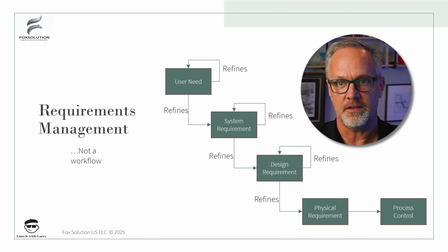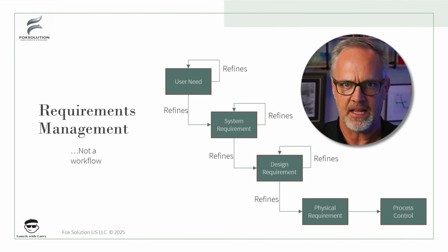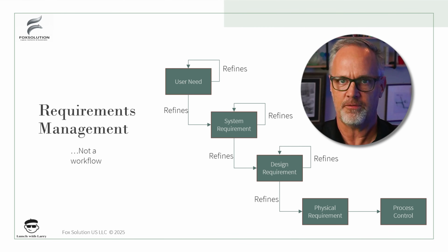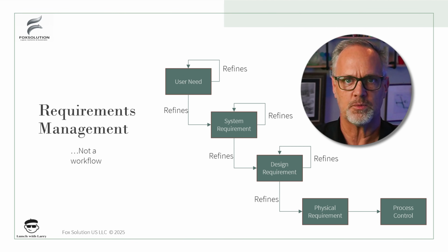So we need all these levels to have a complete view of what our mitigation strategy is. From where we're designing out problems, we have manufacturing mitigations that assure that the physical requirements are met and therefore the design requirements are met. And also we have labeling requirements, which are design requirements as well. So if we have all these levels in the decomposition, we can use those requirements as mitigations to hazardous situations. And that's where we're going to go with this.